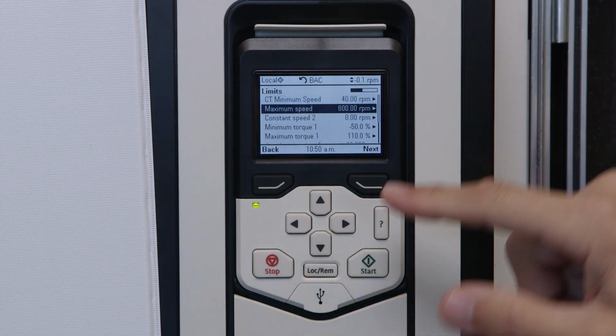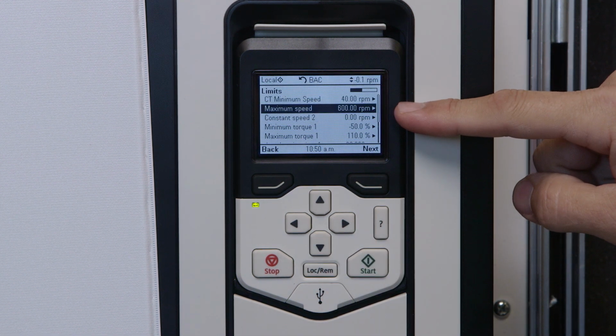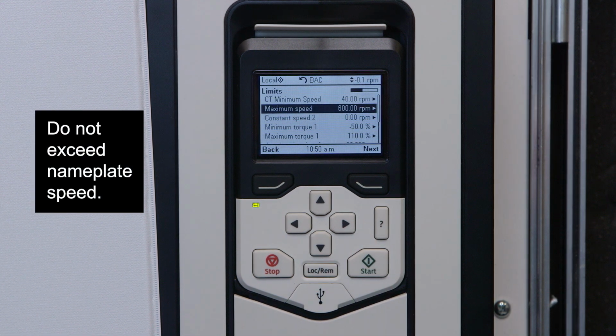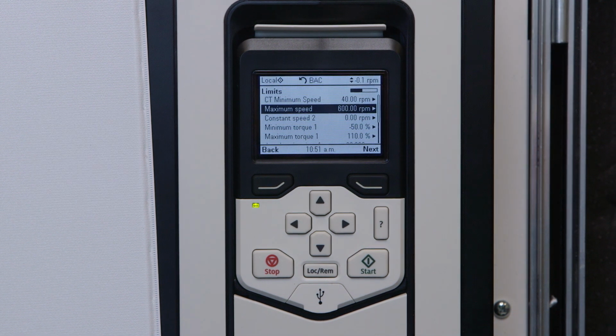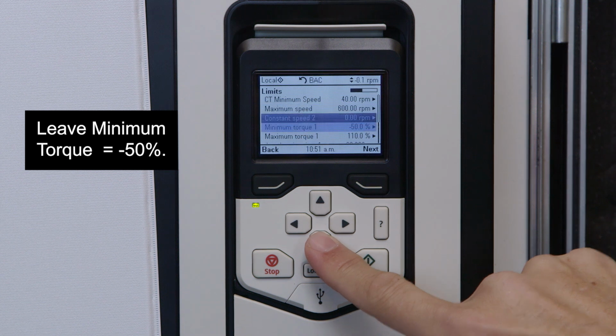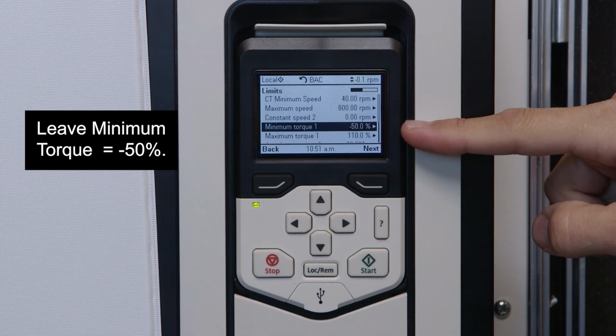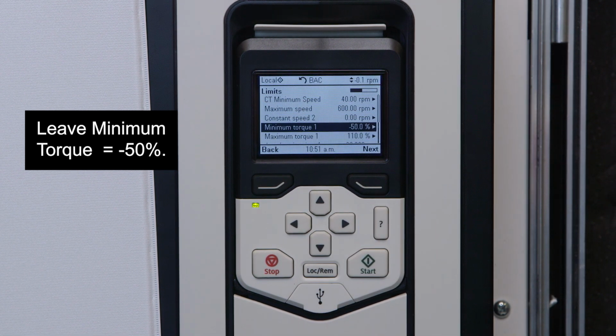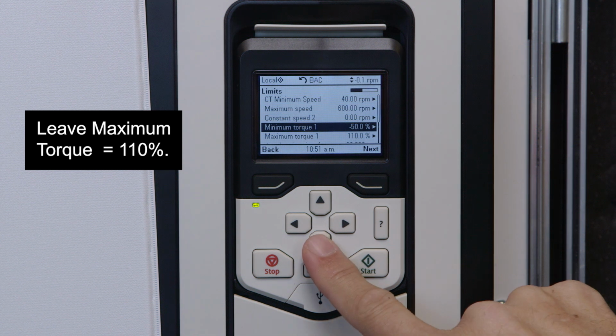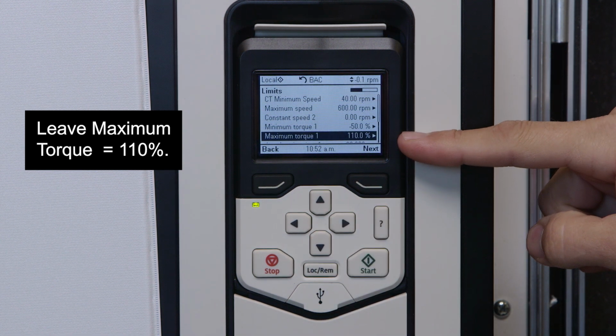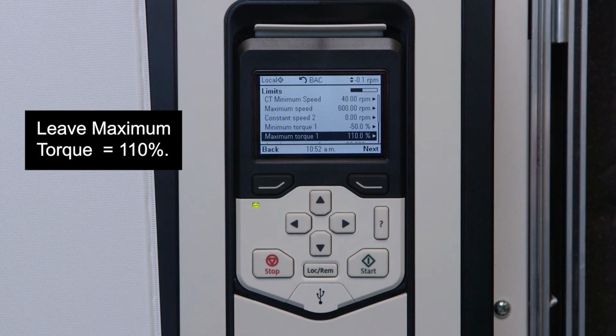The VFD automatically sets the maximum speed value to the nameplate speed. Set this default value or enter the value desired. Do not exceed speed on the nameplate shown in RPM. Do not change the minimum torque. The value should be -50%. Do not change maximum torque. The value should be 110%.